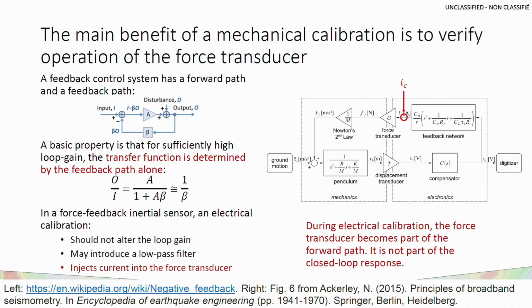In a force feedback inertial sensor, an electrical calibration should not change the loop gain, may introduce a low-pass filter, and crucially, it injects current into the force transducer. On the right-hand diagram, the details aren't important, but you can see the calibration current IC being injected into the force feedback transducer. If you follow that current around to what was the ground motion input, and then out to the digitizer, you realize the force feedback transducer is now part of the forward path, not the feedback, so it doesn't determine the response.